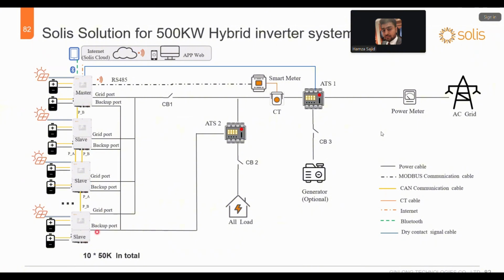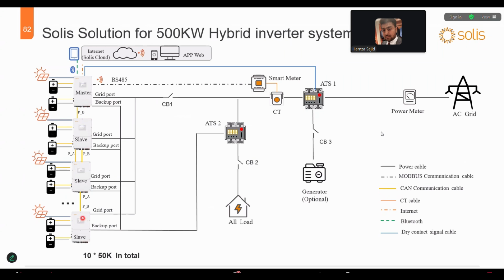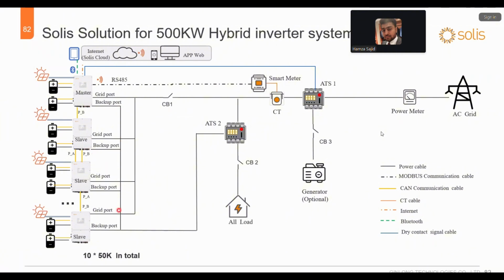And similarly, you can go for cascading. One thing you have to make sure is that the grid port and the grid sequence is similar for the grid input, like RYB; the sequence of the phases should be similar for all of the inverters. And the backup port sequence should also be equal, and that can be paralleled up with the same bus bar, and connected to all the load through the ATS. Okay, and if you are using a generator, you can also use the generator with the help of the ATS. So it can help you with both solutions, with the generator or without the generator. So this is the total overview of the installation.